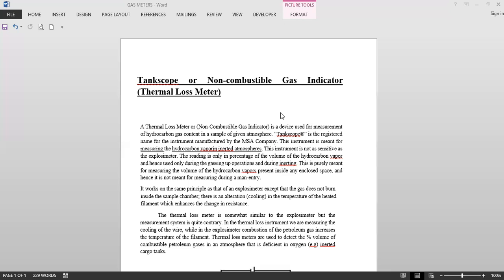Now this instrument is not as sensitive as the explosimeter. The reading is only in percentage of the volume of the hydrocarbon vapor, and hence used only during the gassing up operations and during inerting.